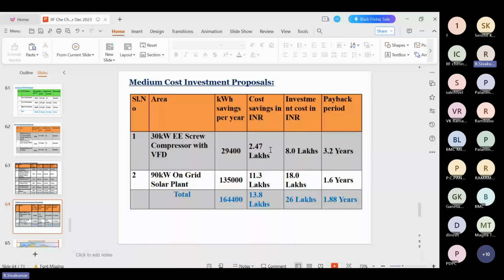And there is a provision in the roof area, so a 90 kilowatt on-grid solar plant can also be suggested. We suggested it through the audit. So 90 kilowatt into 5 units per day per kilowatt into 300 days gives 1,35,000 units that can be generated. This unit generation can be offset in the grid. The investment cost is 18 lakhs and 11.3 lakhs is the benefit. So 1.6 years is the payback period for 90 kilowatt. These two are medium cost investments, because about 2 lakhs is considered a medium cost investment.